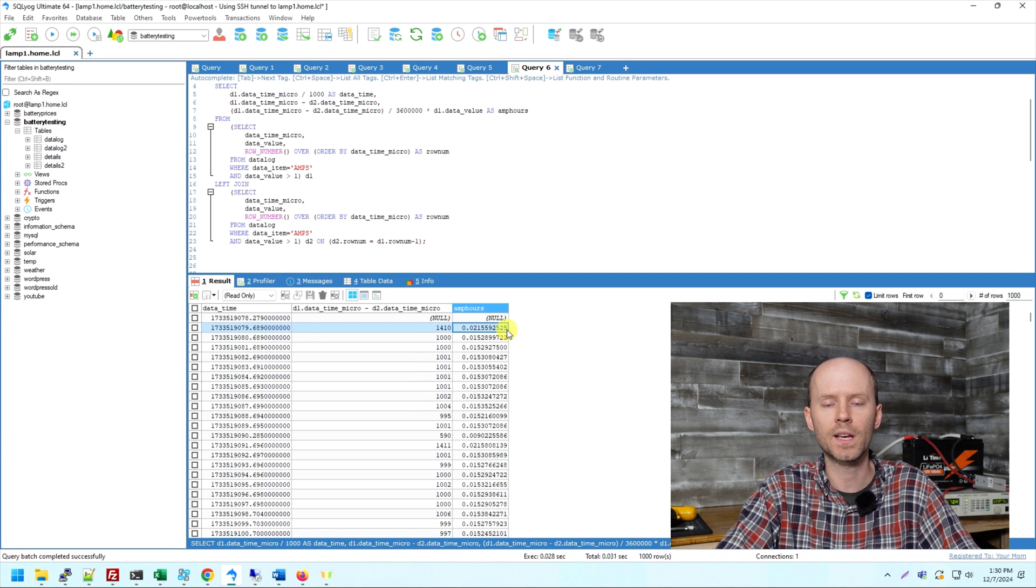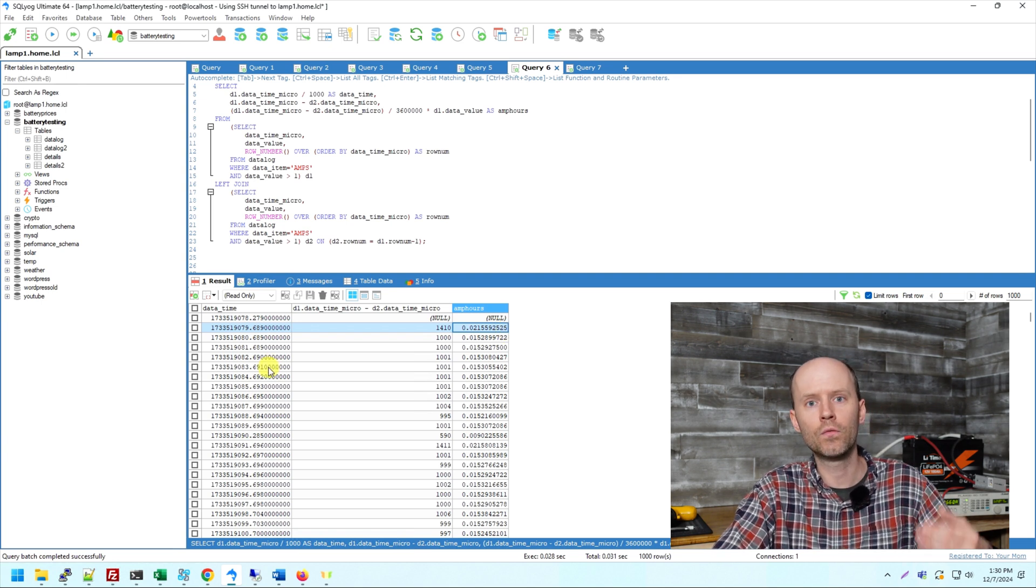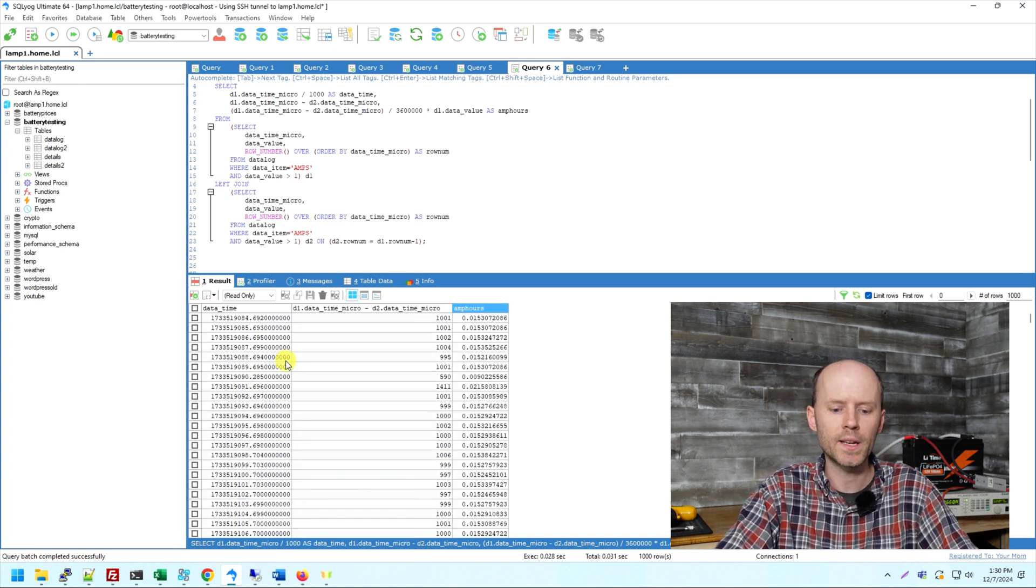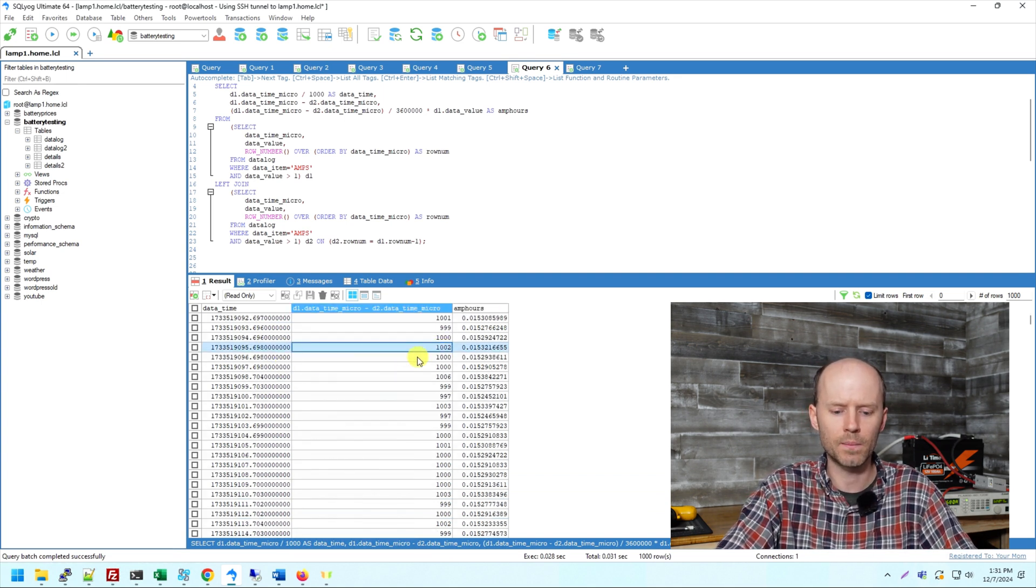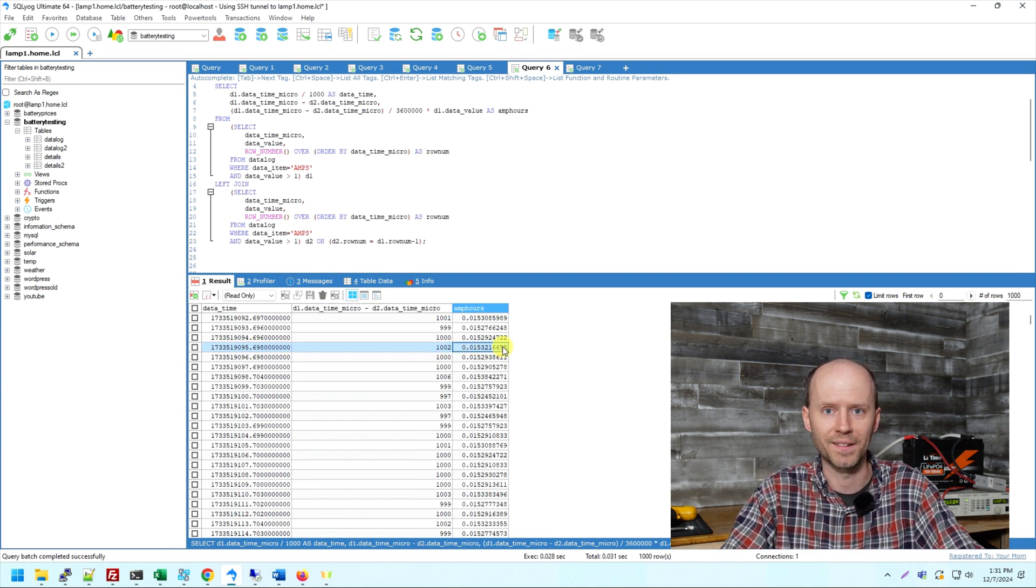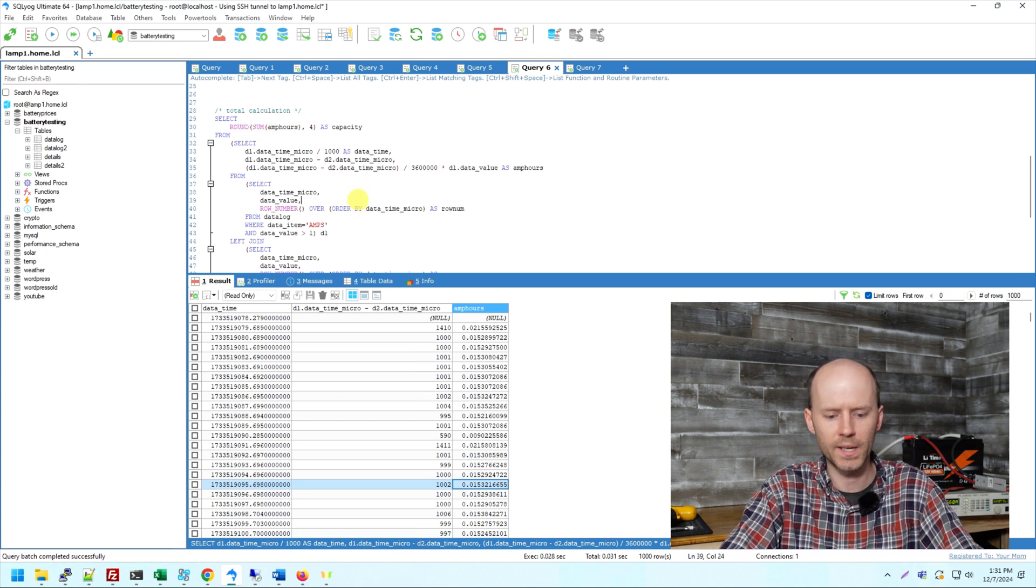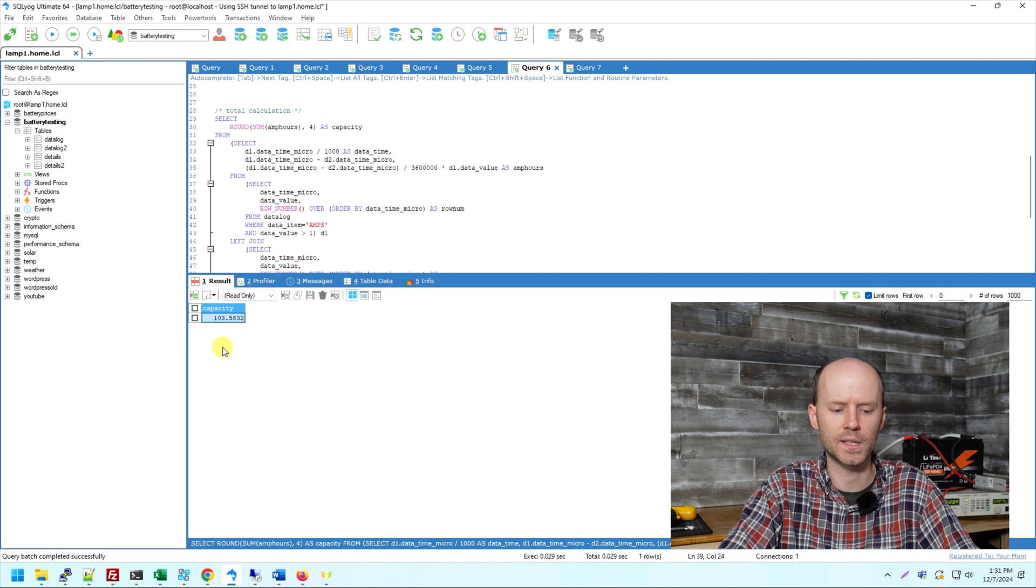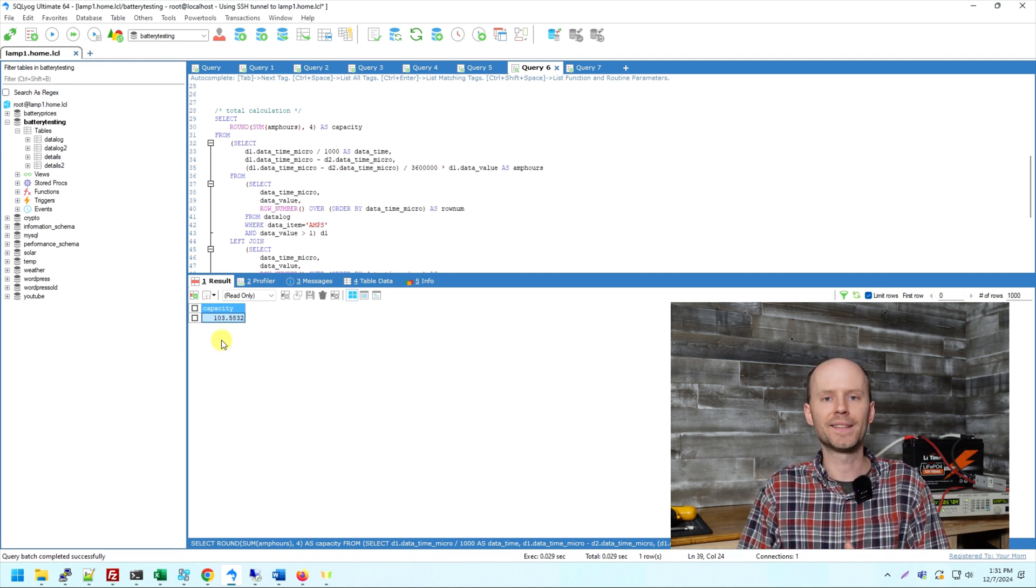I'm doing these calculations to 10 digits of precision. If we continue that process over and over again for the entire duration of the test, we end up with this long series of read events, the amount of milliseconds that's elapsed between each read event, and the amount of amp hours has elapsed in each read event. We can sum it all up, and we can round it to four decimal places, and we get the final capacity of our battery, which in this example was 103.58 amp hours. It's a lot of information to take in. I hope that makes sense.